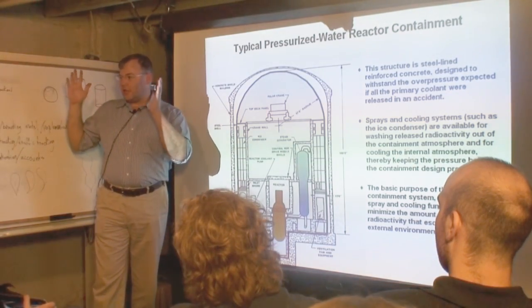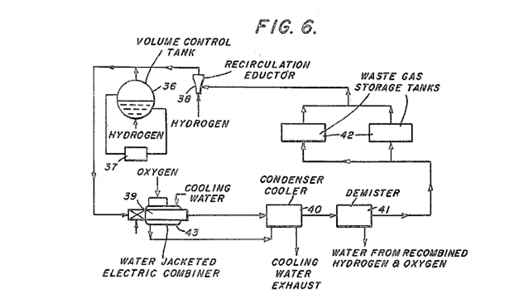Here's why water is not such a great thing for the inside of a nuclear reactor. Number one, it can't hack the temperature. Number two, it's a covalently bonded substance — the oxygen has a covalent bond with two hydrogens, and neither bond is strong enough to survive getting smacked around by a gamma or a neutron. They knock the hydrogens clean off. In a water-cooled reactor, you have a recombiner system that takes the hydrogen gas and oxygen gas always being created from the nuclear reaction and puts them back together. It's a great system as long as it's operating and pumping. At Fukushima Daiichi, the pumping power stopped. Water was still getting busted apart, and hydrogen being really light will dissociate and sit at the top of the vessel.